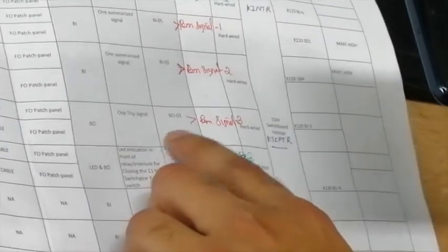So the ABB relay is getting this signal for indication, and also for trip, because on this signal, on differential protection or REF protection, the 11 kV breaker also has to trip. But the protect relay is also directly tripping the 11 kV breaker. And at the same time, the protect relay sends this signal over a fiber optic link to the 132 kV relay. So for that we have configured LED number 3, I think. Yes. So for this signal, in order to check the signal on the 132 kV side, we have configured LED number 3 on the 132 kV protect relay.